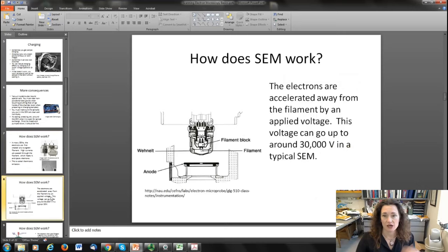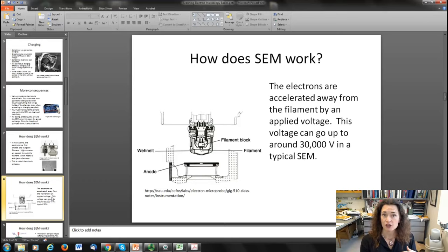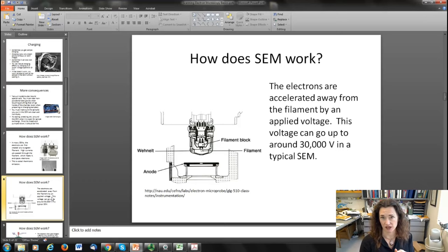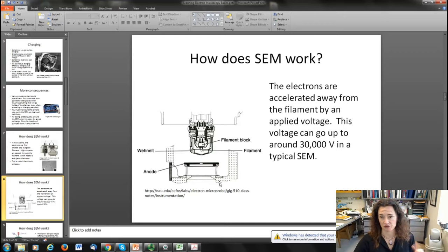Once the electrons are created, they're accelerated away from the filament by an applied voltage to pull them down towards the sample. This typically goes up to 30,000 volts in an SEM, and you can vary the voltage. For example, if you're trying to avoid charging, you might drop your accelerating voltage down to say 5,000 volts. Whereas if you're trying to get x-rays out for chemical identification, you might increase that voltage to get all the x-rays you need. The voltage is variable. You have a filament and a voltage applied between the electron source and an anode that accelerates the electrons away from the filament.